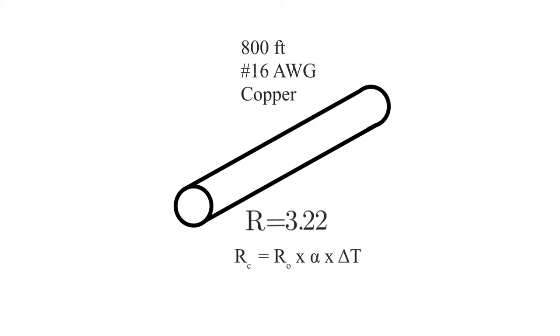So what we're going to use is this formula here. R sub C is equal to R sub O times alpha times delta T. Now we're going to look at what these are. This is your original resistance, which is the 3.22 ohms. This symbol here is our coefficient of temperature, and this means the change in temperature from the 20 degrees that we've calculated out so far.